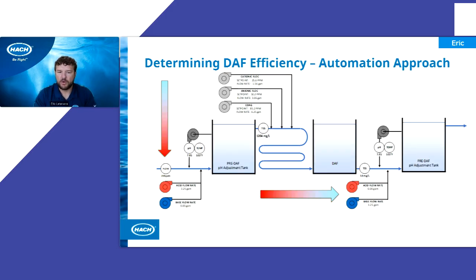So an automated approach to that would be, on the left-hand side, your pre-DAF tank. Oftentimes on the industrial side of things, we'll see an EQ tank where they're doing some sort of pH control, whether an acid and a base. So they're monitoring pH and temperature at that tank. Coming out of that tank is going to be your TSS, going into the DAF. So now we're measuring TSS continuously, and we can make a determination, based on TSS, of how much floc we need to add, how much coag we need to add. So we have more of a feed forward control.